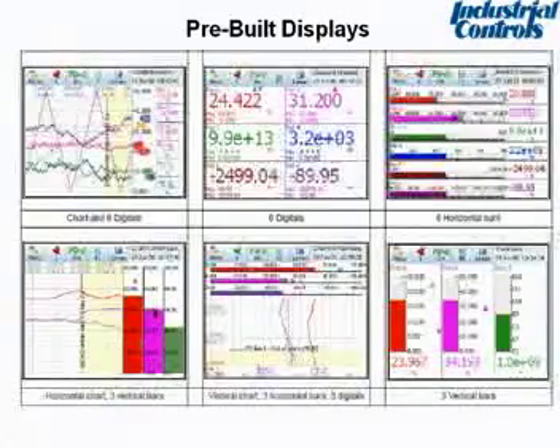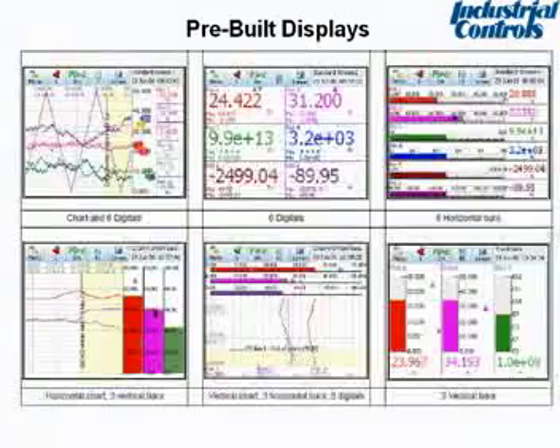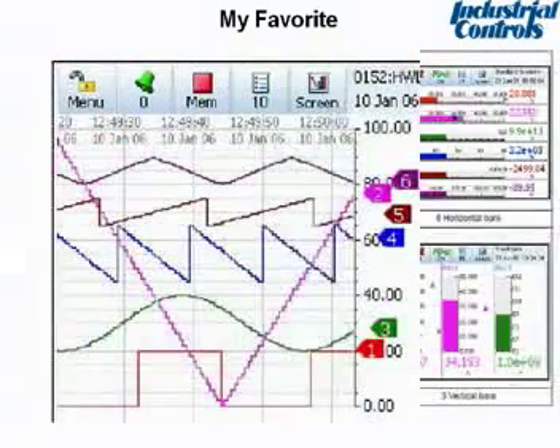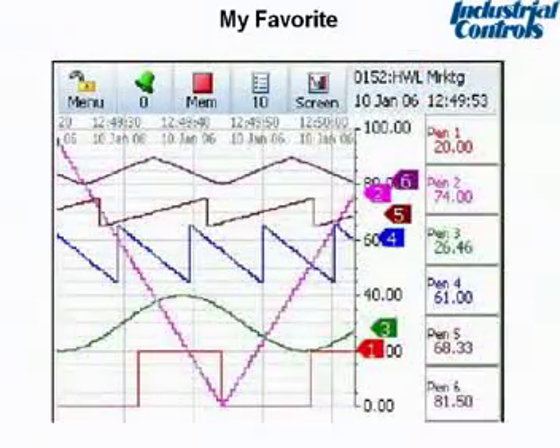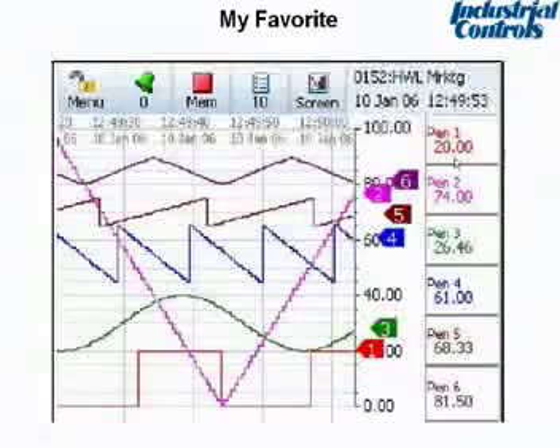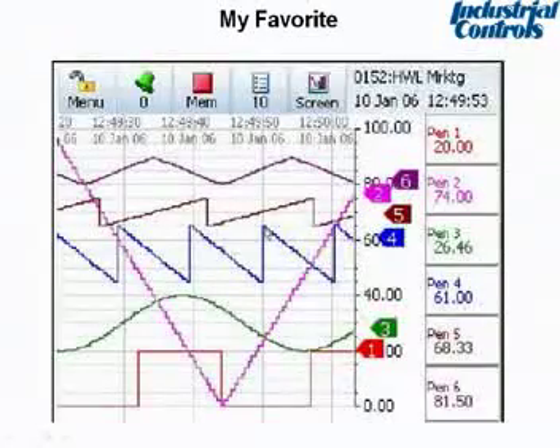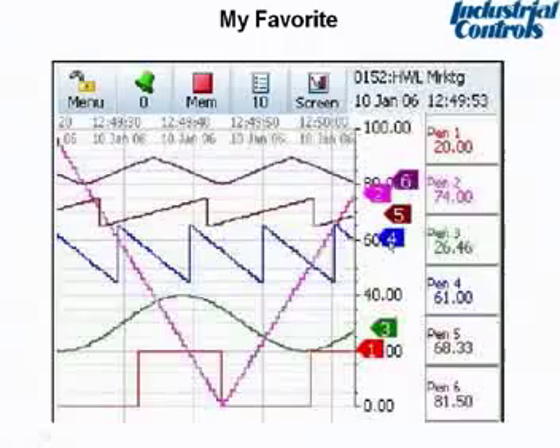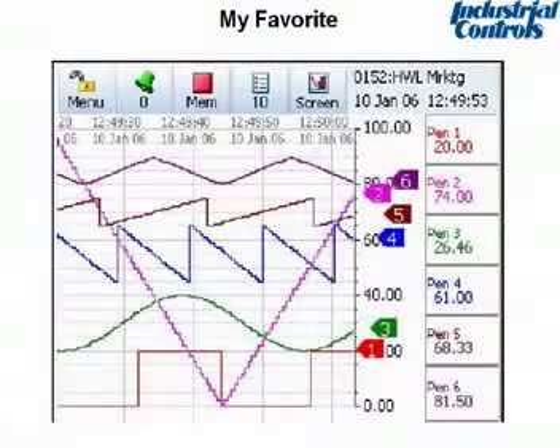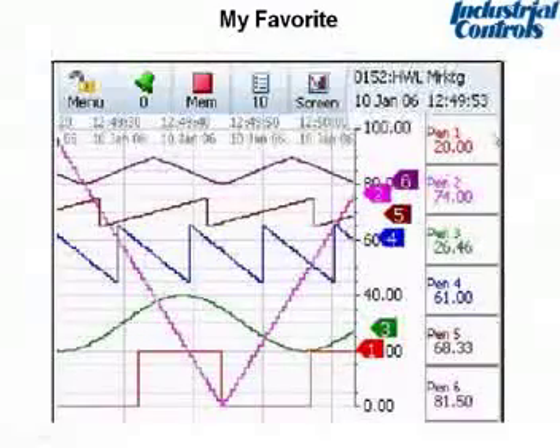But here's the key. All these display formats are pre-built. These are not custom graphics. These are pre-built displays that you pick during configuration, and then all you do is put the point names you want in each one of those displays. So pretty nice stuff. My most favorite one is the horizontal trend with the pens and scale, and then the live digital value. The operators seem to like this because when they come over to the screen, instead of finding the blue pen or the purple pen and interpolating as to what the value is, they just match up the pen color, the pen trace, and the digital, and that way they know the live digital value of that particular parameter. And by the way, you can configure these to be your own tags, obviously, instead of just calling them pen 1, pen 2.